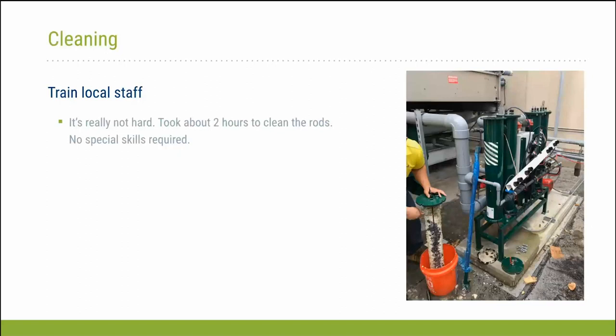Once we had our O&M contract in place and we had the initial service done by our on-site people, we also awarded a contract to the vendor so that they could come out on a regular basis, do the cleaning, and also check the settings. We had a cleaning by them a month ago, and they adjusted some of the settings based on their recent test of our incoming water. The silica in our water was higher than they saw the last time they were out, at about 22 parts per million, and so they turned the TDS reading down to 1,500 microsiemens.